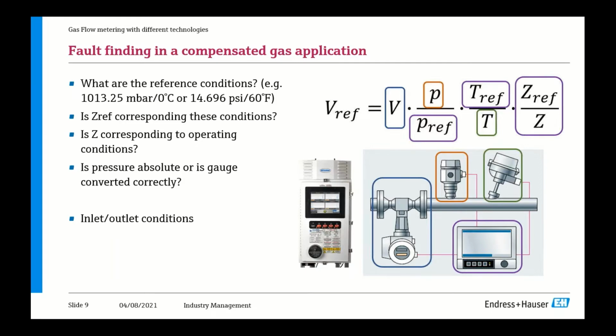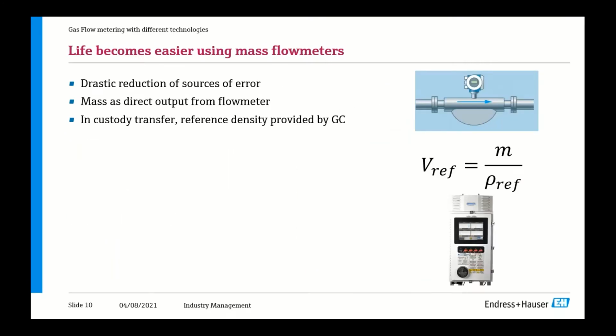And the beauty is now, if we go to the next slide, we see the perfect simple answer is actually direct mass flow measurement. So we will see later the measurement of Coriolis. You have direct mass measurement, and you just divide mass by the reference density. And you get the reference density again from a gas analyzer, as you see one from our own company. And the other error source is mass. And with the Coriolis, you can achieve 0.25% of reading in mass terms. And this is unachievable with all the other technologies that we're going to see right now.